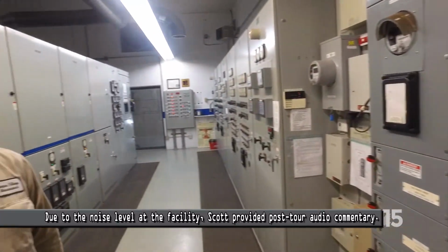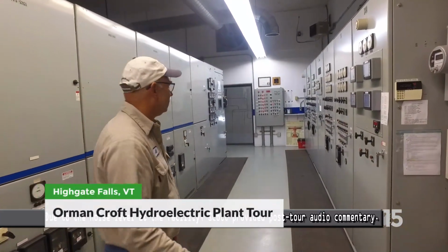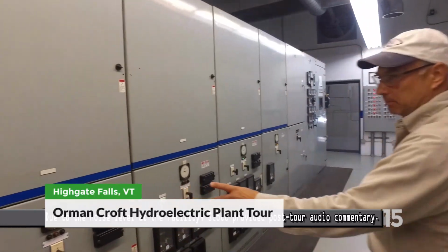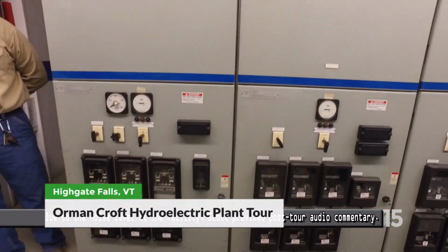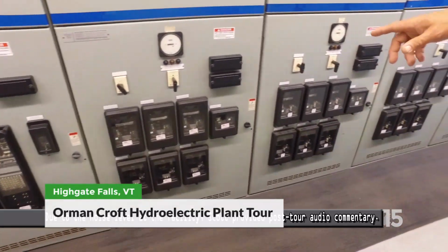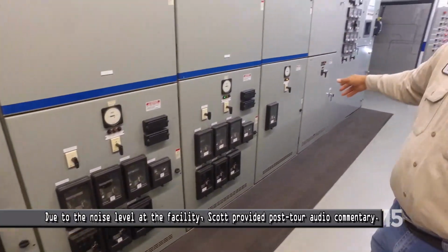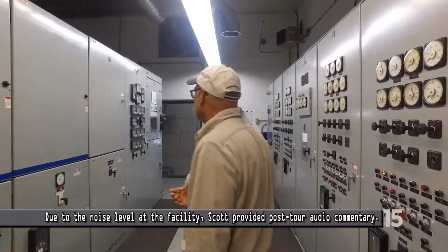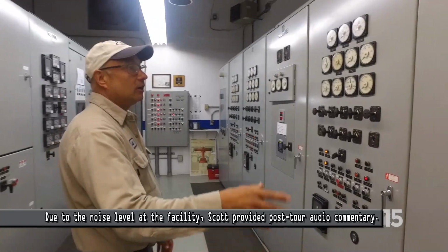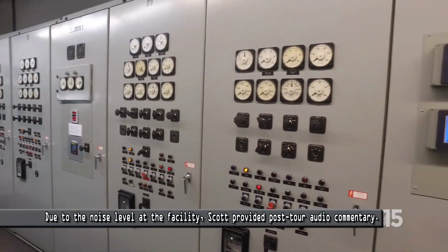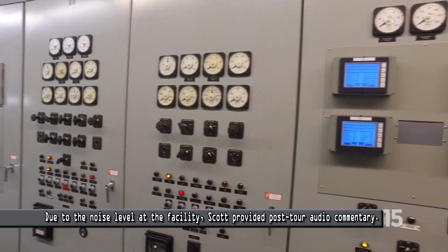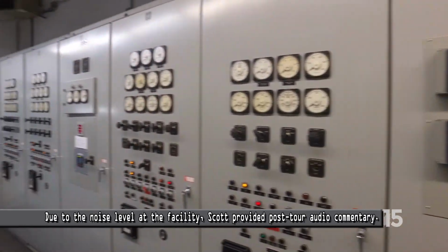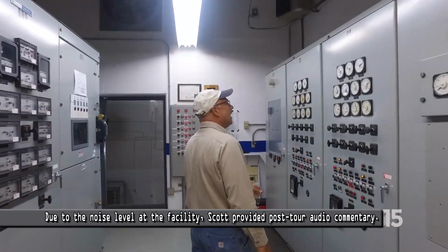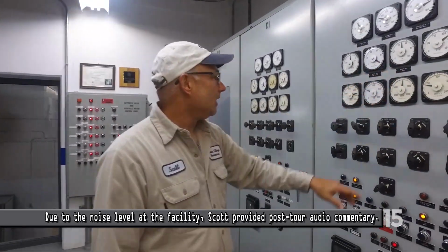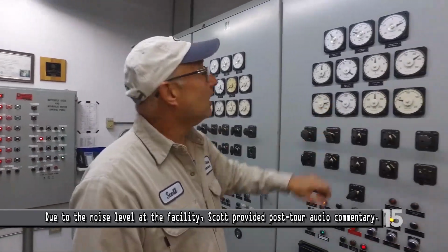Then we have the circuit breakers for each unit plus a tie breaker. These tie us in, they tie the electricity from the plant into the grid. Then we have the switchgear for units 1, 2, 3, and 4. This is how we start the units. We sync them to the system, and then when we lock in the breaker, that's when the breaker locks in and sends the power out to the grid.